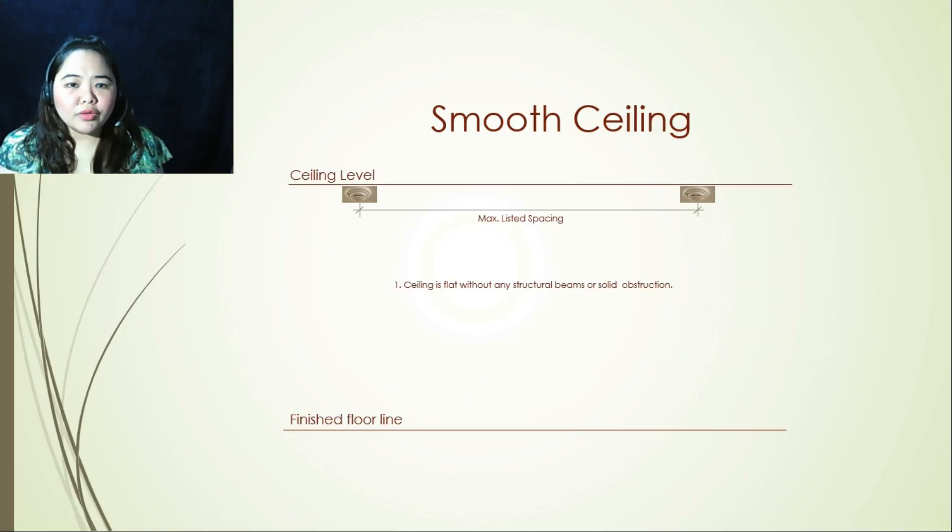So we have our first slide. As you can see in the illustration, we have a smooth ceiling. So a smooth ceiling is a flat ceiling without any structural beams or solid obstruction. If we have a smooth ceiling, we will follow maximum listed spacing. So if we're going to use NFPA standards, that's going to be 15 meters, but you can also refer to the manufacturer.